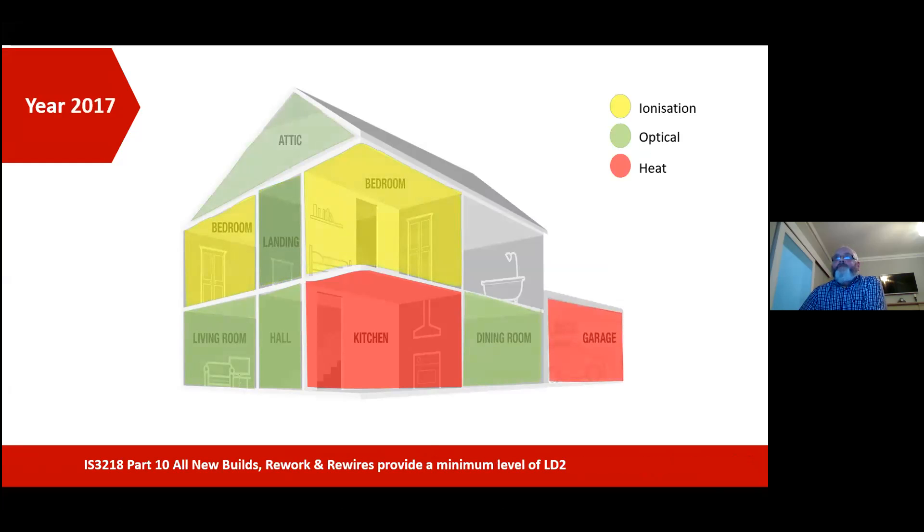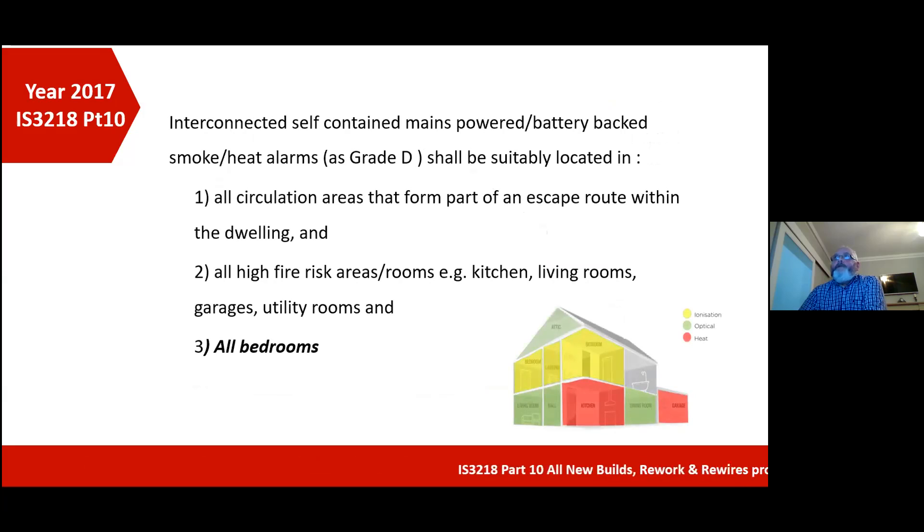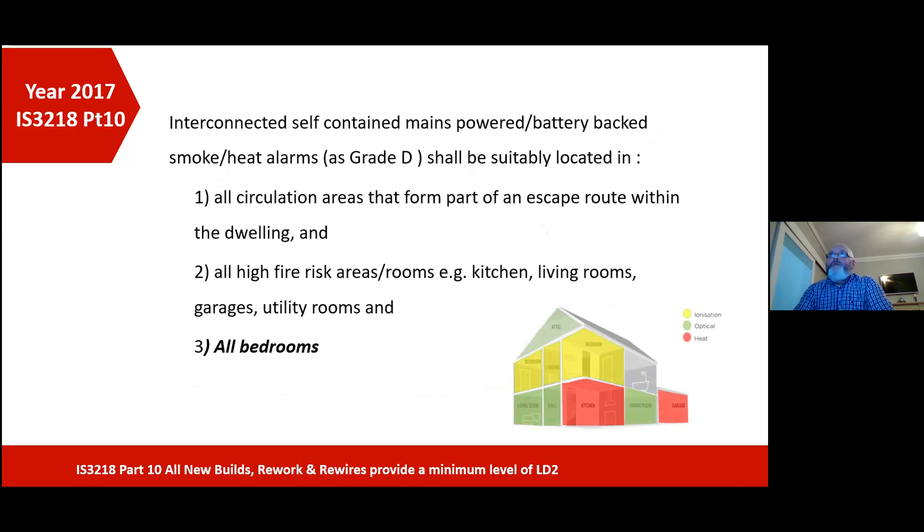So in 2017 when the review came again, you can see by the graphic on the screen, we have a lot of detectors in residential premises at this stage. Interconnected self-contained mains powered battery backup smoke and heat alarms as grade D — which is mains powered units — in all circulation areas that form part of the escape route, dwelling, and all high risk areas, for example kitchens, living rooms, garages, utility rooms, and in all bedrooms. That's a major advancement in relation to 2017 compared to 2006.